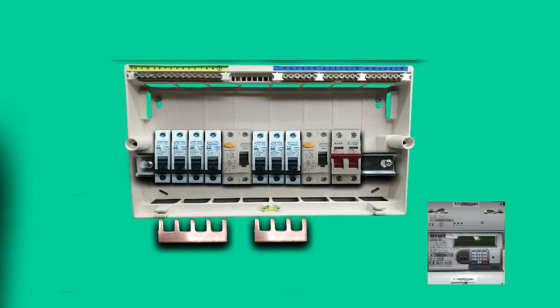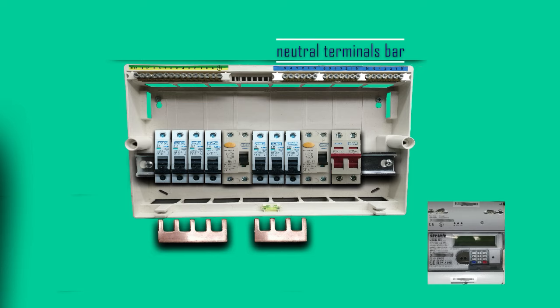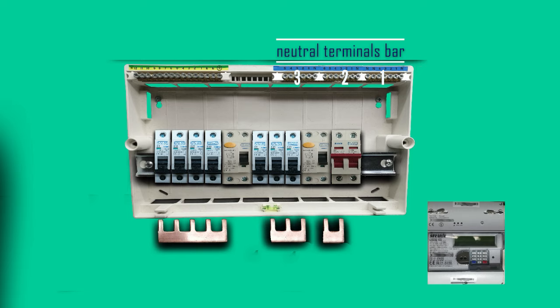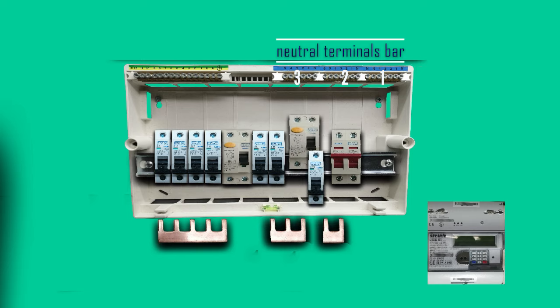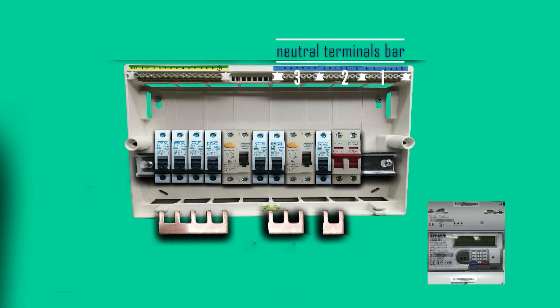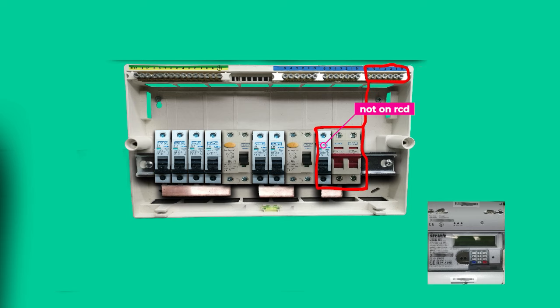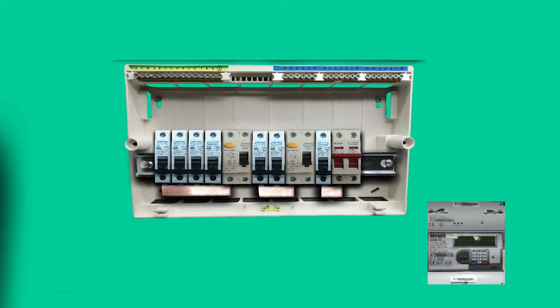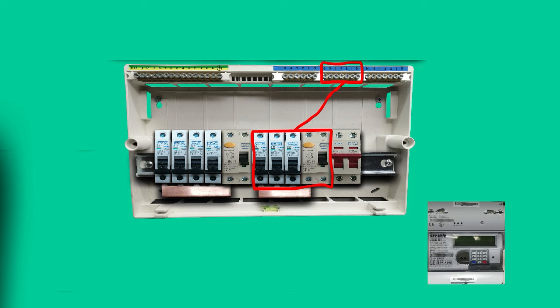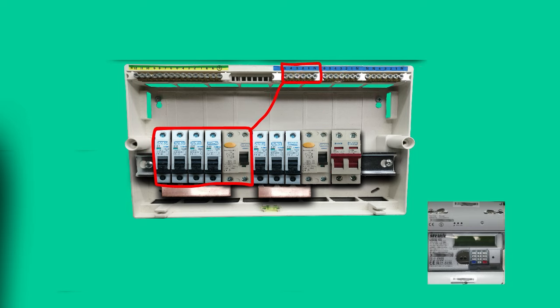On top of the consumer unit we've got a neutral terminal bar where we connect the neutral wires from the cables, and the terminal bar is divided into three parts or sections that correspond to each RCD and circuits that are connected to this RCD, as well as the main switch. The first part is for the main switch and any other MCBs that are not protected by RCD, if you fit them between the main switch and RCD. The second section is for the first RCD and its circuits and the third one for the next RCD. All the neutral wires from the circuits need to be wired to the right sections of the neutral bar.